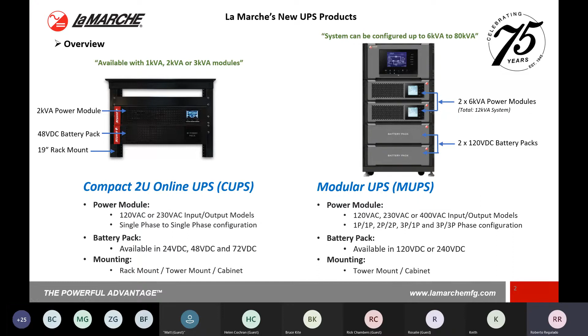On the modular UPS, we have it set up with different power modules and various voltage ratings. We do have single phase to single phase, split phase to split phase, 3-phase to single phase, and 3-phase to 3-phase configurations. Depending on which one of those power modules is selected, you can have 120 VAC to 230 volts, 400 VAC, and a few other variations in between that are selectable depending on the power module. The battery packs are only available in 2 selective sizes, 120 volts DC or 240 volts DC. And again, these are only mountable in a rack type cabinet. And if you have just a single module solution, they can be mounted in that tower mount, which we will see a little bit later on.